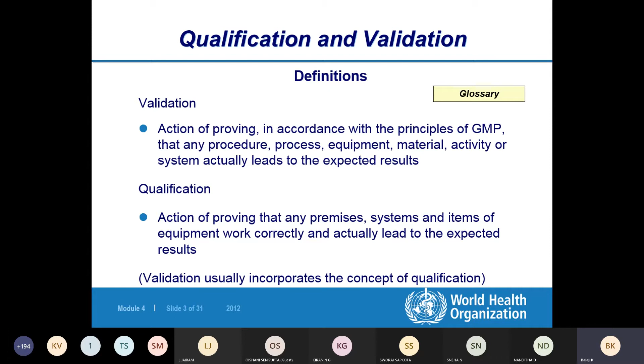Principle: qualification and validation are an essential part of GMP. This is a very important part of GMP as well, because all the procedures you have written, such as how to operate the autoclave, the basics of how to operate the autoclave come from the autoclave validation package. What temperature you have to set? Usually you know the autoclave temperature, right? It is 121.1. Why does that 0.1 degrees Celsius come? Suppose you don't know, if you convert that into Fahrenheit, it is about 250 Fahrenheit. When you convert Fahrenheit to Celsius, centigrade, then that 121.1 degrees comes into the picture. And what is the need for pressure there? It is 15 lbs. In terms of kg per square centimeter, it is 1.2 kg per square centimeter.